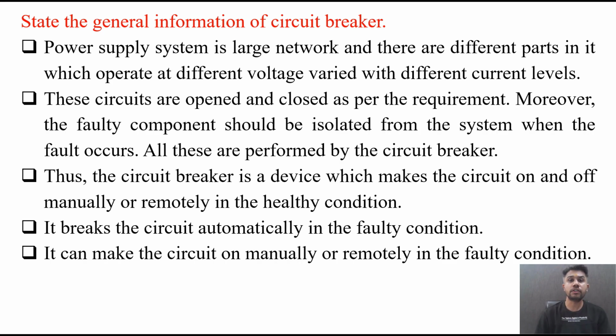State the general information of circuit breaker. In a power supply system, it is a large network and there are different parts in it which operate at different voltage levels as well as different current levels. These circuits are opened and closed as per the requirement. Moreover, the faulty components should be isolated from the system when the fault occurs so that the healthy system works properly. All these are performed by the circuit breaker. Thus, the circuit breaker is a device which makes the circuit on and off manually or remotely in the healthy condition. It breaks the circuit automatically in the faulty condition. It can make the circuit on manually or remotely in the faulty condition. So this is the basic or general information of circuit breaker.